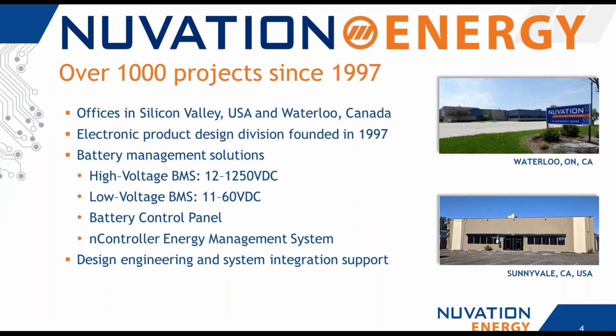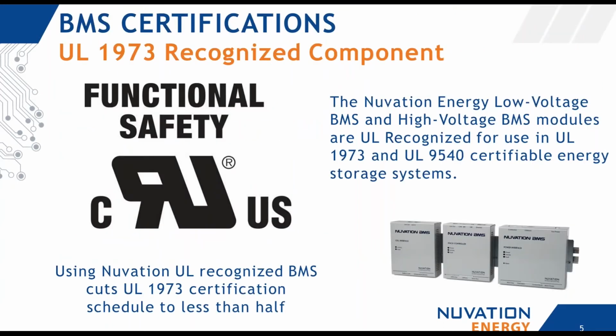And it's through that integration support that I found myself sometimes supporting remote islands in the middle of the Pacific. Our BMS recently received UL recognition for UL 1973 by completing both UL 991 and 1998. Our BMS is the world's first configurable BMS for recognition under UL 1973. What I mean by configurable is that it's configured to work with different chemistries, different battery manufacturers, different stack voltages and topologies without having to reopen any of the UL 991 or 1998 reports. UL actually didn't have a process for completing functional safety of a configurable BMS in this way. Now that we've achieved that, this BMS cuts the UL 1973 certification time in half and reduces cost.